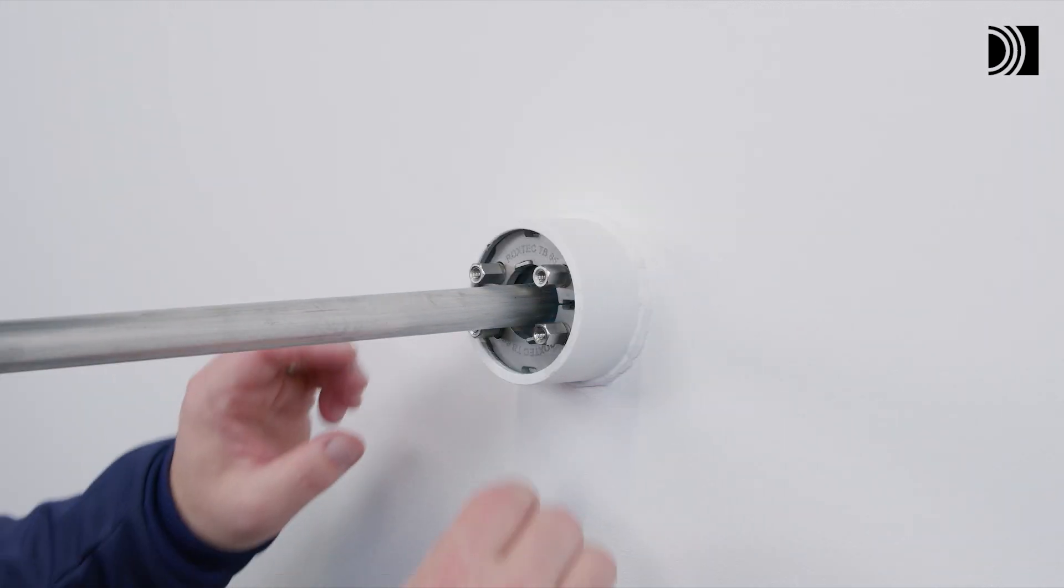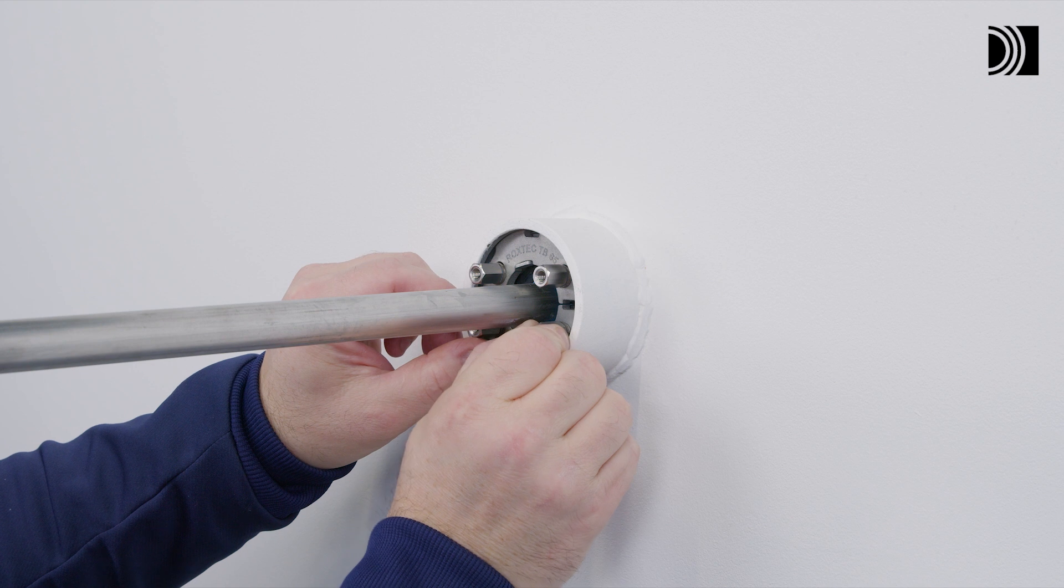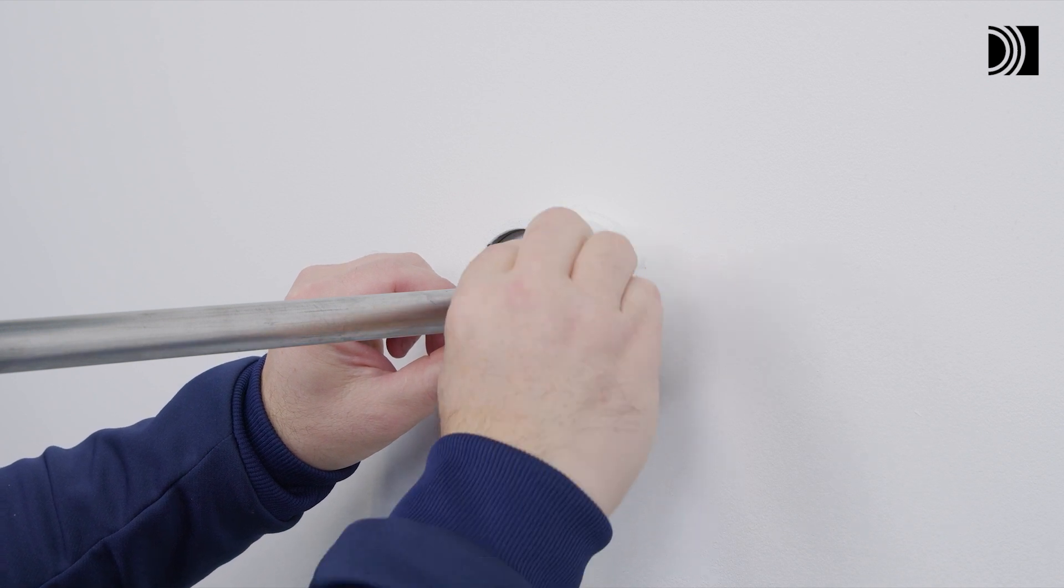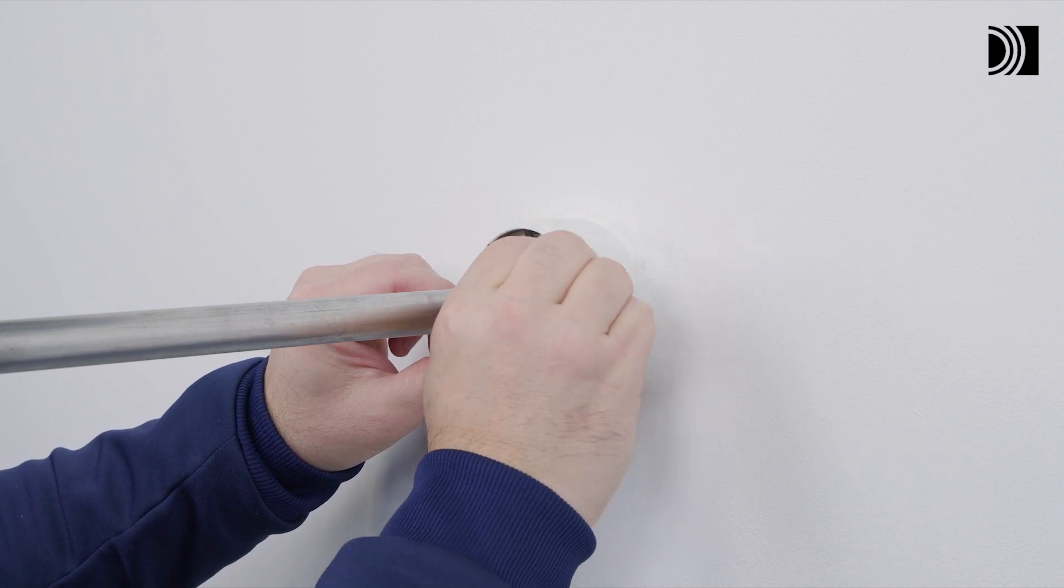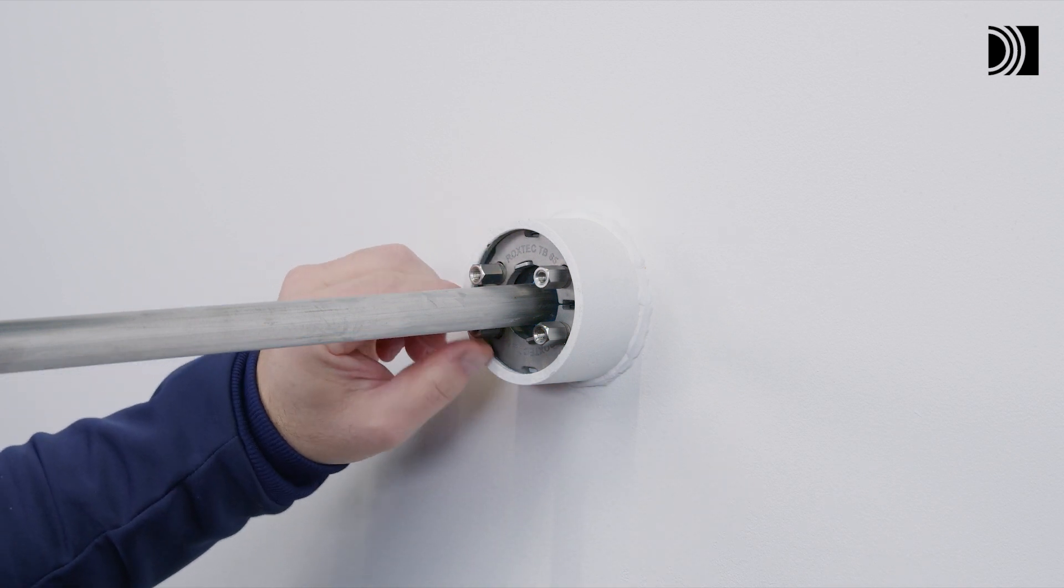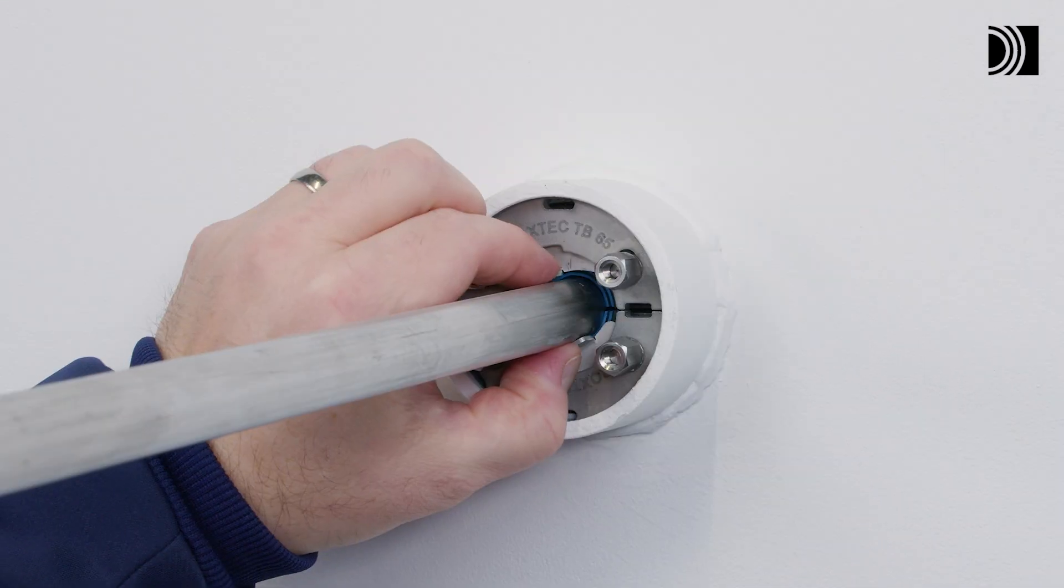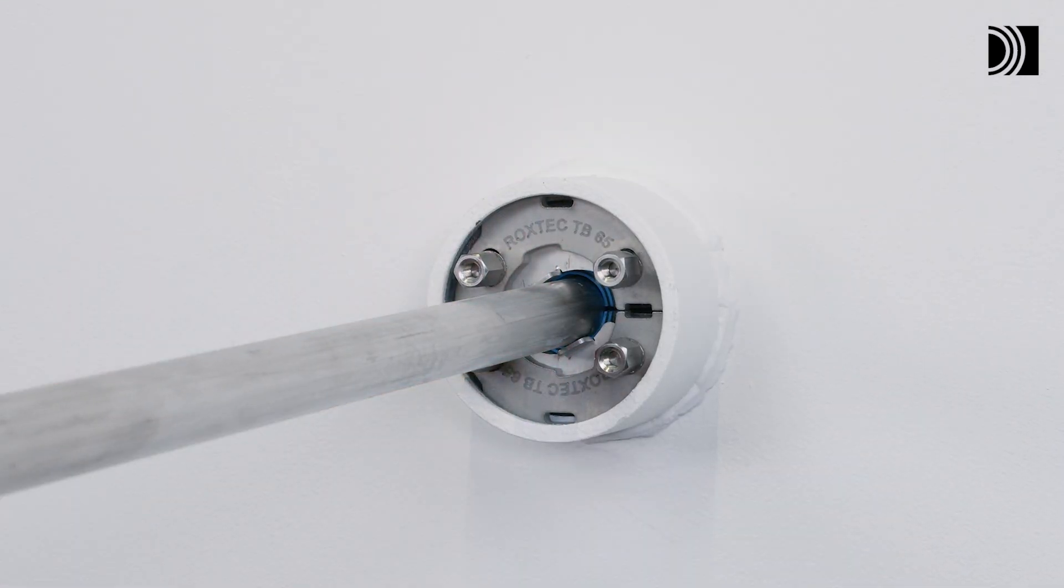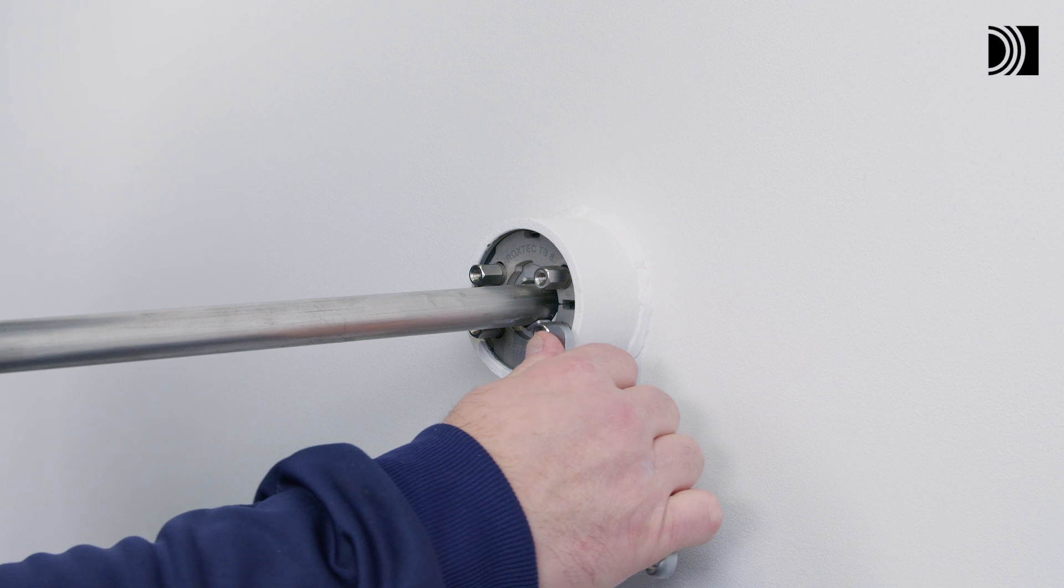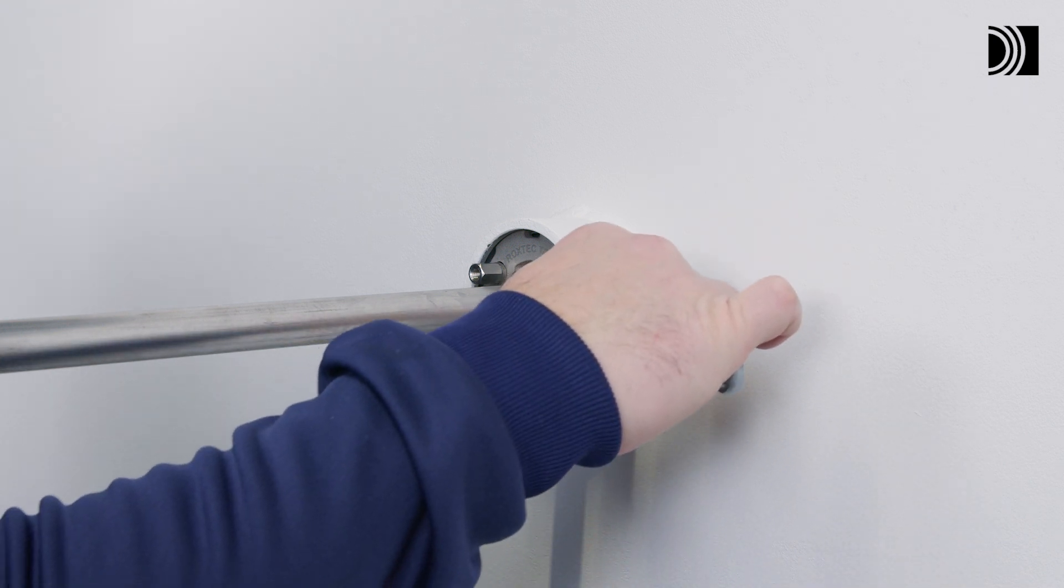Tighten the seal. Ensure that both fittings are as far into the groove as possible and tighten the nuts with your fingers. Adjust both rotation fittings to the cable or pipe. Tighten the nuts firmly. The nuts shall be tightened crosswise and in small steps.